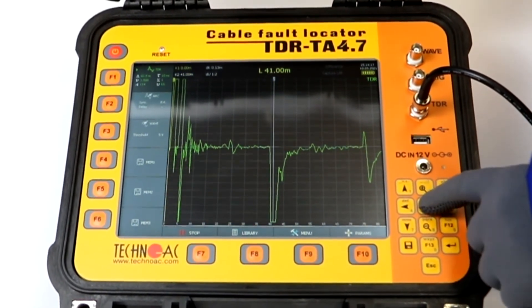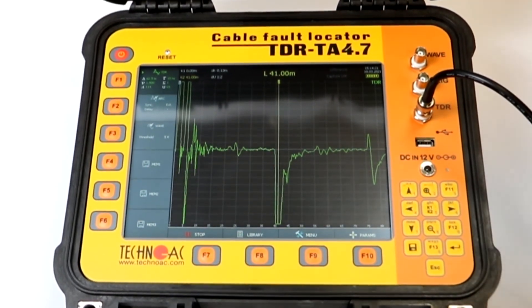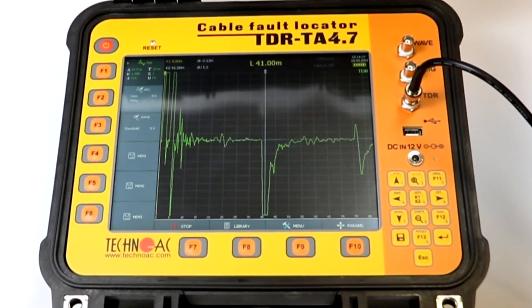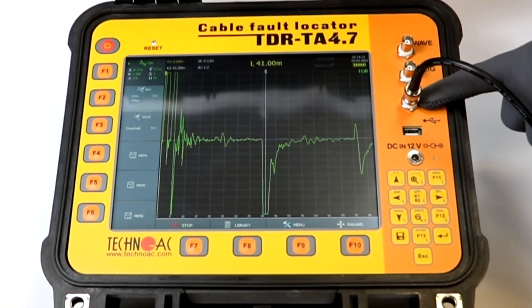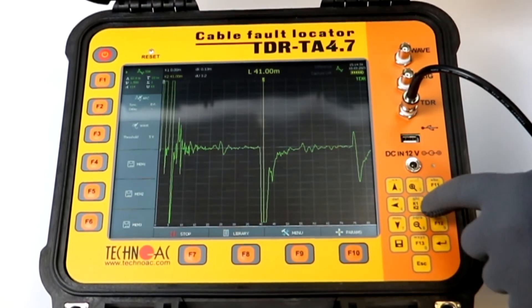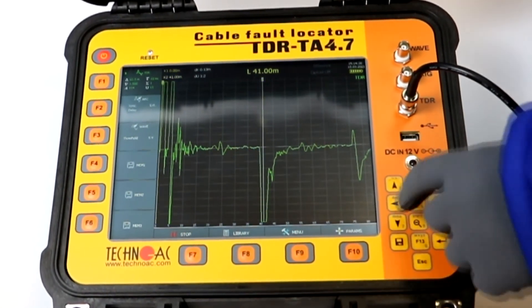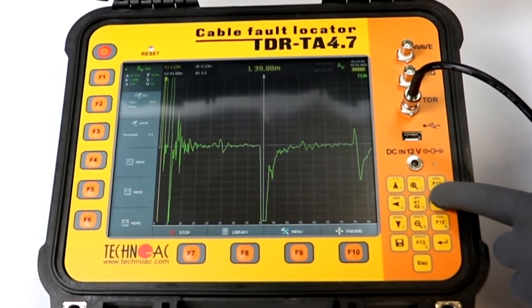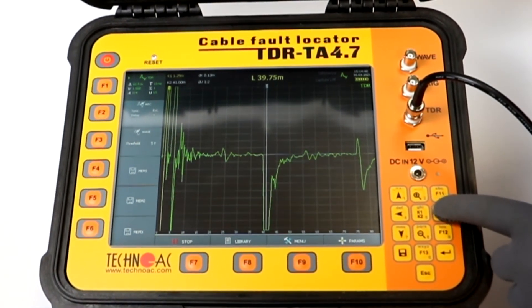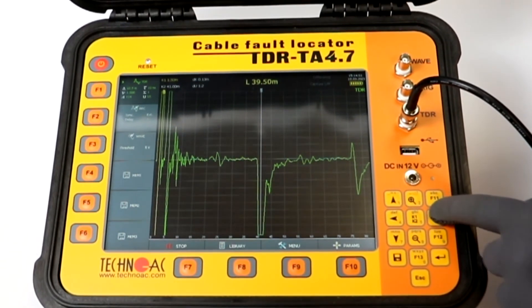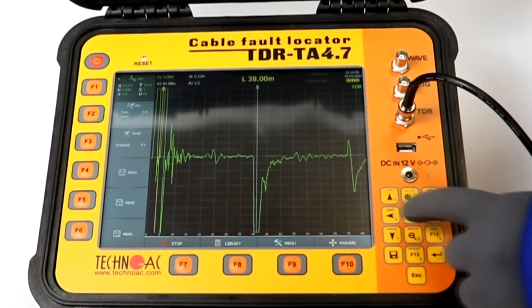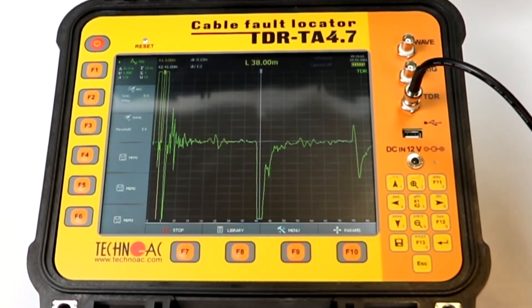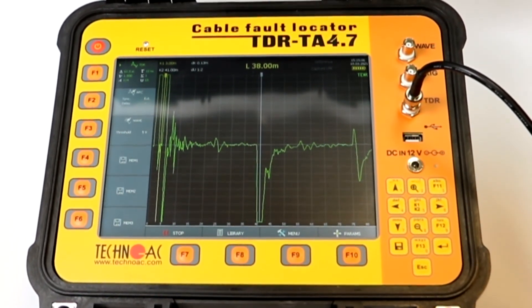By pressing K1/K2, we can switch between cursors and adjust the measurement. Note that the distance to the fault is measured from the point of connection to the actual spot of the fault. So by moving Cursor 1 three meters, you exclude the length of the cable supplied with the TDR. We had 41 meters, so we set it to 38 meters — that is the distance of the fault from the point of connection.